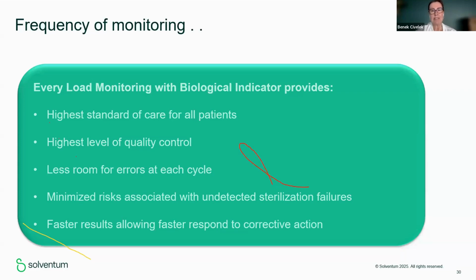We are always discussing the frequency of monitoring, because we always say the best practice is every load monitoring. So what can every load monitoring provide to the patient and the staff? First of all, the highest standard. We will have the highest standard for all patients and the highest level of quality control, and it will be a best practice to have in your quality assurance programs. There will be less room for errors at each cycle, and of course we will minimize the risks associated with undetected sterilization failures, and you will have faster results, and this will enable you to respond with faster corrective action.